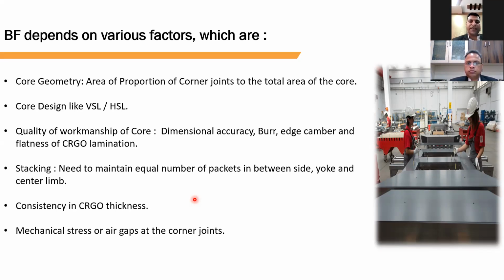What is the meaning of equal number of packets? Our CRGO design is controlled by the center limb number of pieces and stack height. So the CRGO supplier needs to provide lamination in such a way that whatever number of laminations we supply in the center limb, we need to supply in equal proportion in the side and yoke. For example, if I'm supplying 5 pieces in the center, then 10 pieces should be in the side and 10 pieces should be in the yoke.